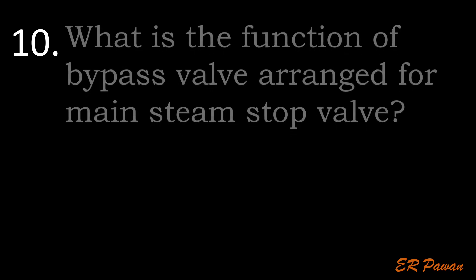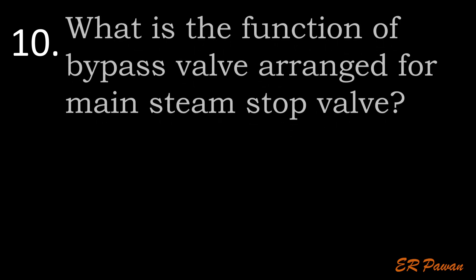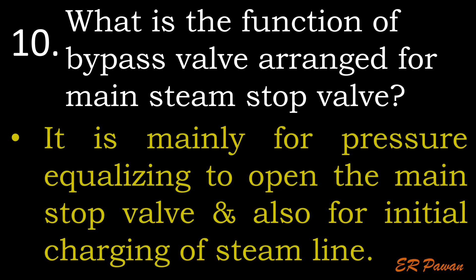Question 10: What is the function of the bypass valve arranged for the main steam stop valve? It is mainly for pressure equalizing to open the main stop valve, and also for initial charging of the steam line.